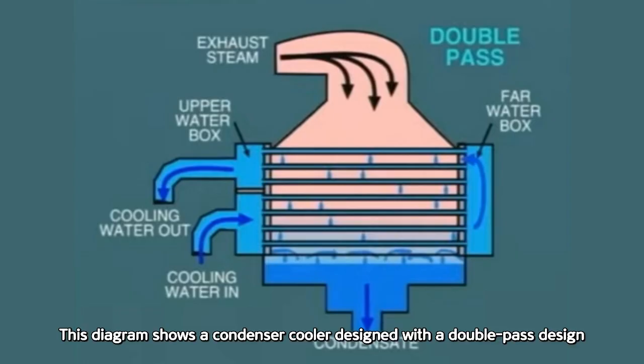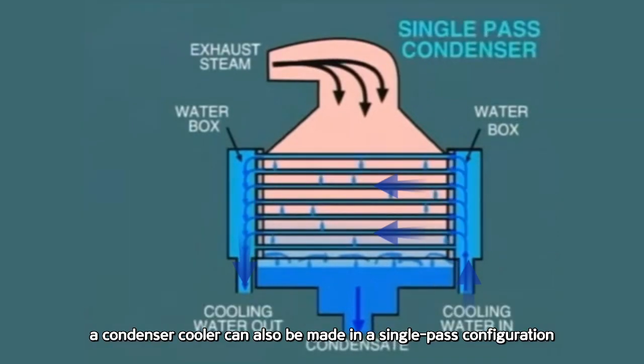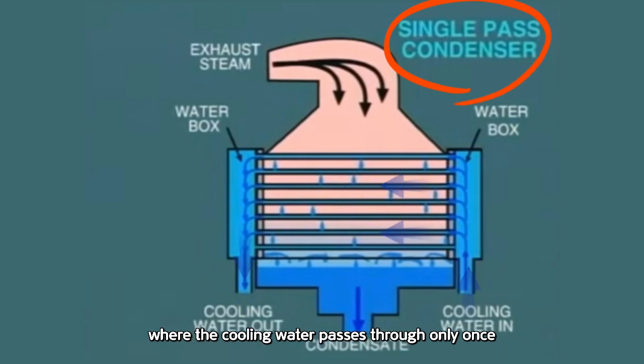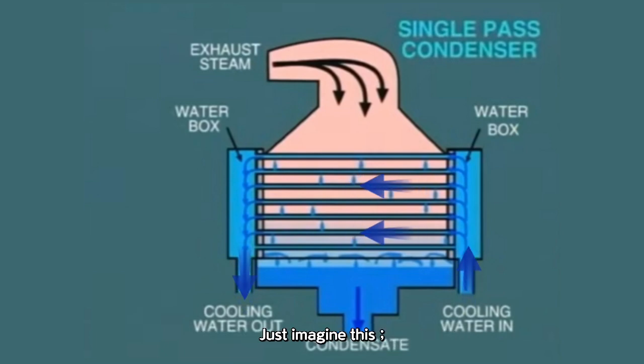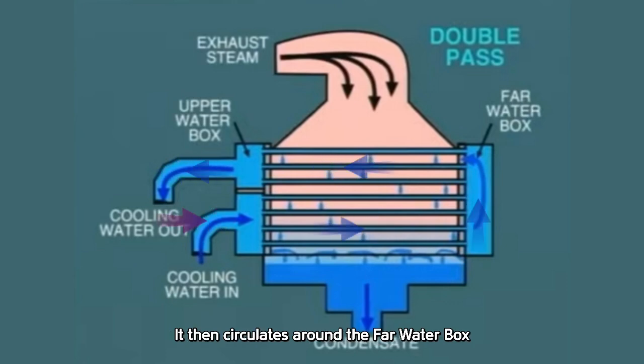This diagram shows a condenser cooler designed with a double-pass design. Depending on its design, a condenser cooler can also be made in a single-pass configuration, where the cooling water passes through only once. Now, let's continue with the explanation. Just imagine this. The system is currently in a vacuum state, and the cooling water enters through the pipeline at bottom section. It then circulates around the far water box before exiting through the cooling water outlet.